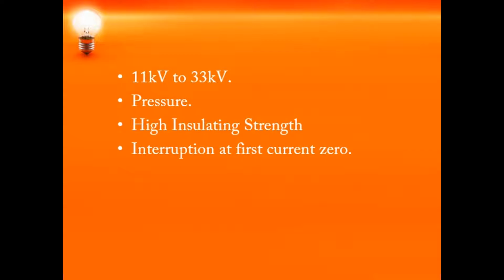Similar to other circuit breakers, this circuit breaker also has a fixed contact and a moving contact. But these fixed and moving contacts are completely enclosed in a permanently sealed vacuum casing. This circuit breaker is mainly used in the voltage range of 11 kV to 33 kV. The pressure inside the vacuum chamber is maintained at approximately 10 to the power minus 4 torr. And this vacuum circuit breaker has two phenomenal properties.